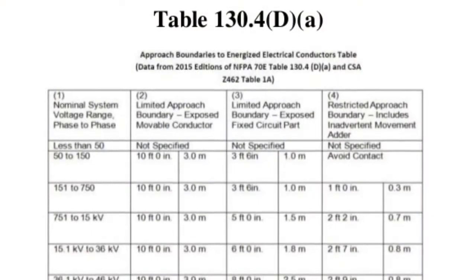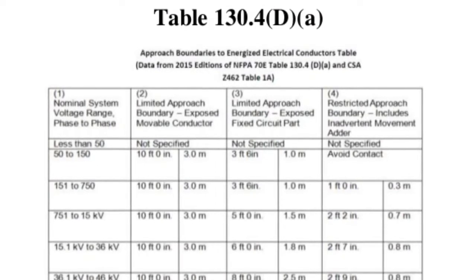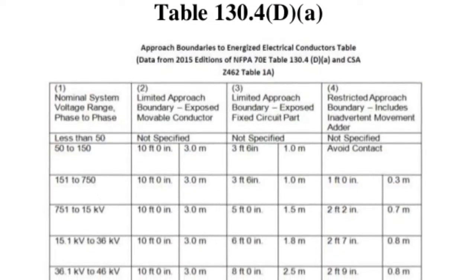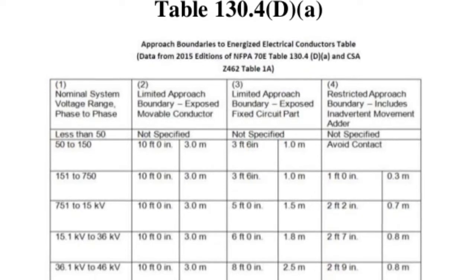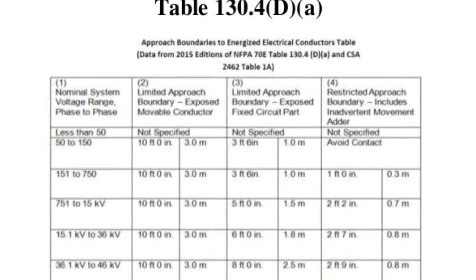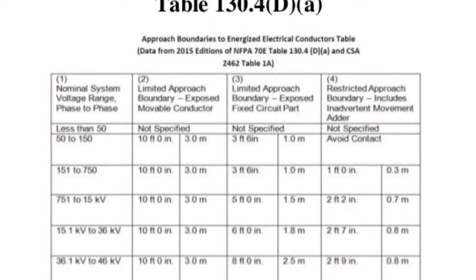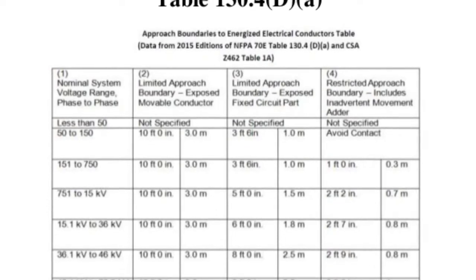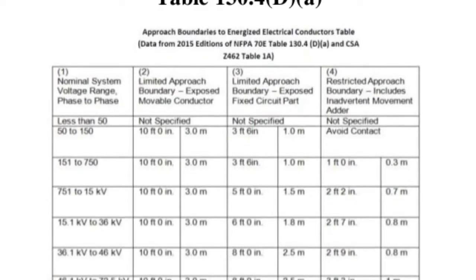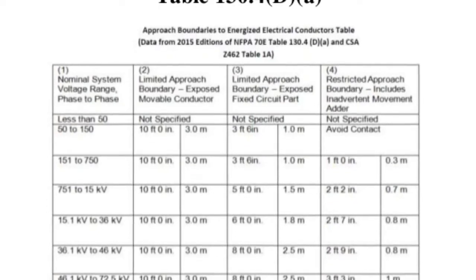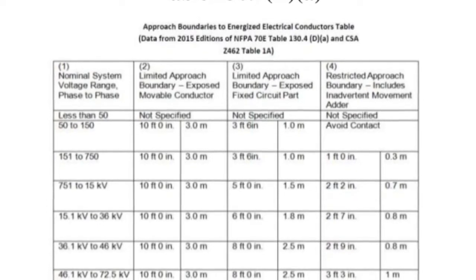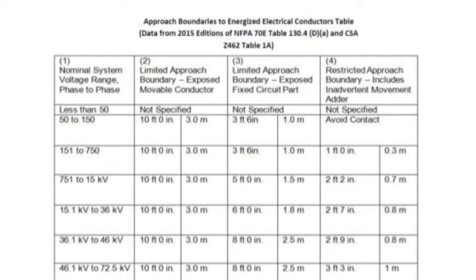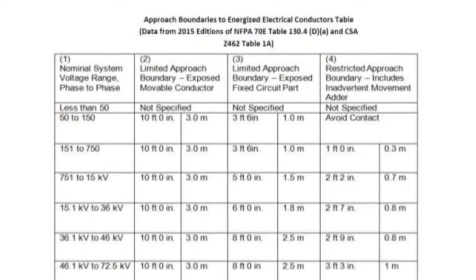Table 130.4 D-A in the NFPA 70E defines shock protection and approach boundaries for exposed energized electrical conductors for alternating current systems. The table shows nominal system voltage in column 1, limited approach boundary in columns 2 and 3, and restricted approach boundary in column 4. This table, along with the NFPA 70E, can be found in the safety reference job in Procore.